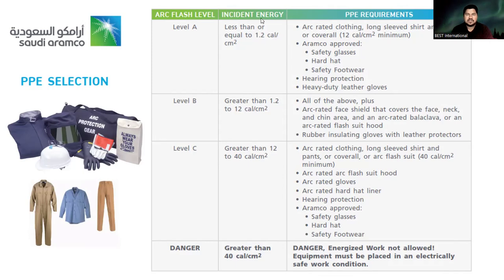If the incident energy calculation is 1.2 calories per square centimeter, remember that it's very important information. The arc rated clothing, long sleeve shirt and pants or coverall, 12 calories per square centimeter minimum, and all other PPE should also be Aramco approved.